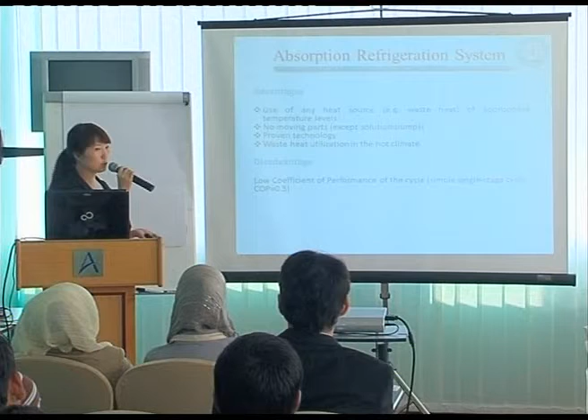As we have mentioned before, in hot climate, cooling is more in demand. Thus, in this way, waste heat utilization can be realized through the absorption refrigeration system. But the disadvantage is the coefficient of the performance of the whole cycle is relatively low. Single stage cycle is about 0.5.